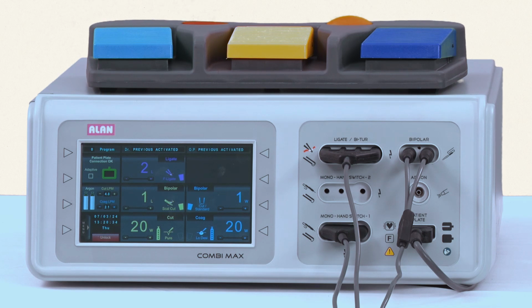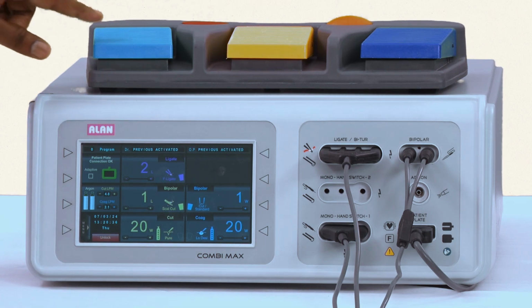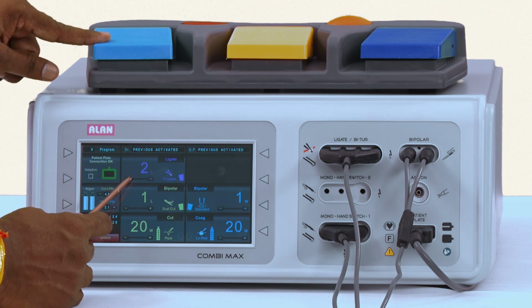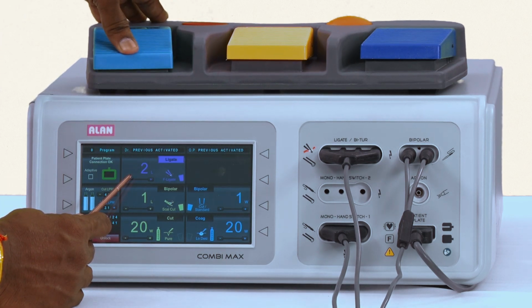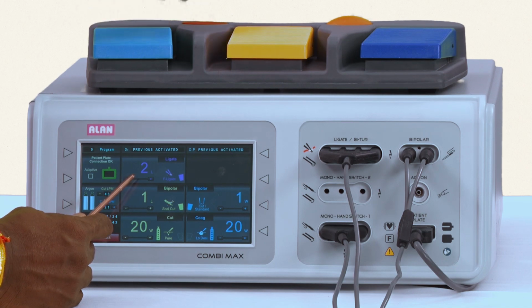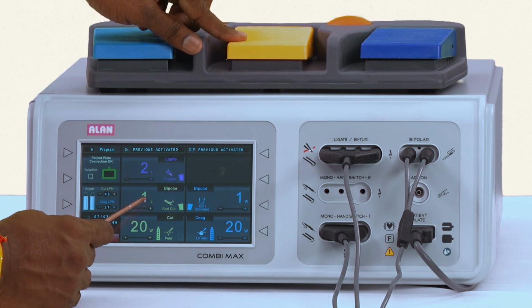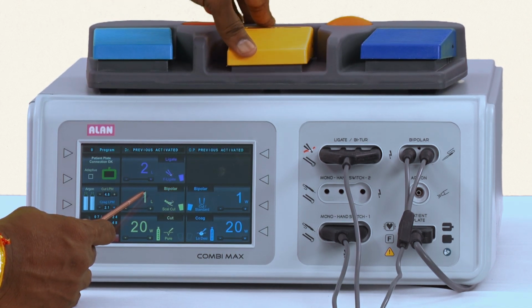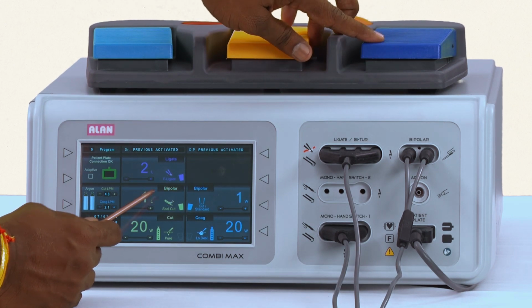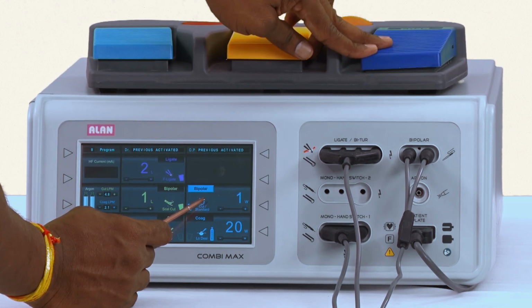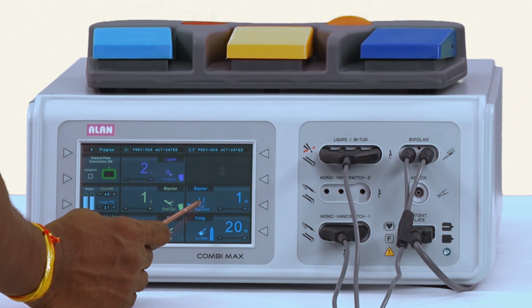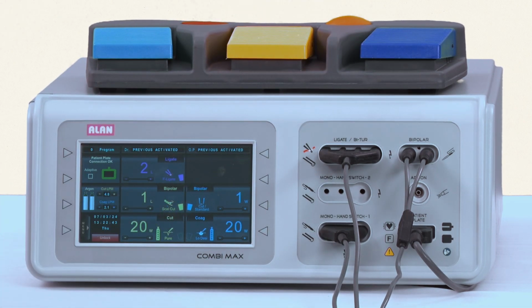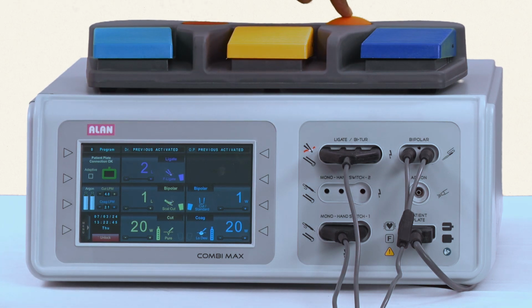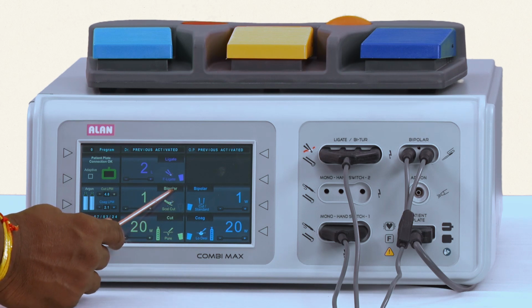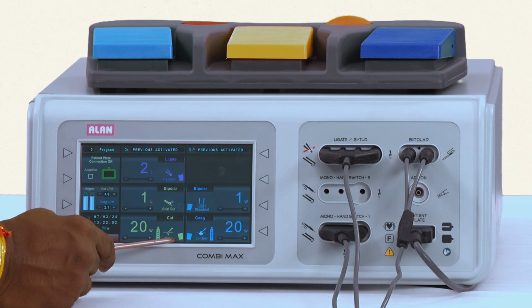Since the unit is ready, we will look into the foot switch. This light blue pedal is assigned for ligation, that is vessel sealing. This yellow pedal is used for bipolar cutting, and this dark blue pedal is assigned for bipolar coagulation. Now, if you want to use monopolar, simply press this orange button and you can witness that the foot switch icon shifted from bipolar to monopolar.